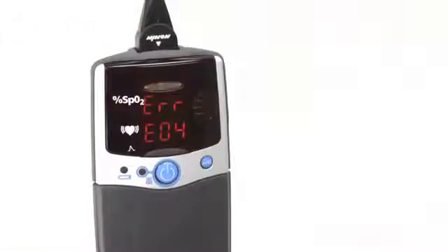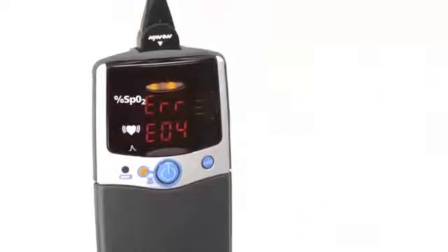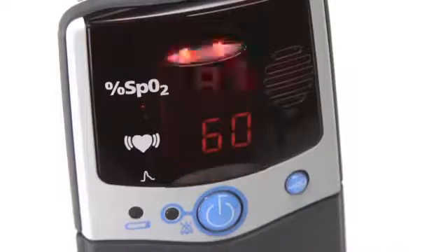Other alarms may occur on the oximeter. You can silence the audible alarm with the on-off button. Immediately notify your clinician or technical support contact. The oximeter will record the time and date of any alarm in its stored data, along with regular oxygen saturation and pulse readings.